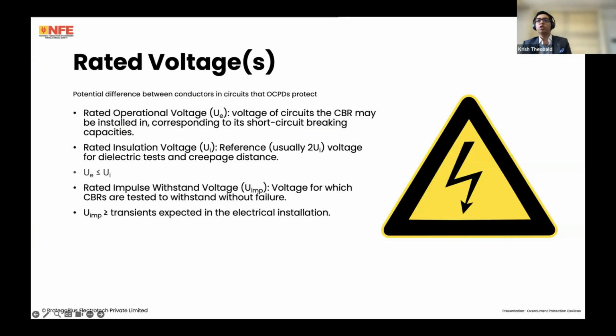There's also a rated insulation voltage, which is what is used by manufacturers for testing, for the dielectric test and the creepage test. Usually it's a reference voltage, so they test at 2 times the rated insulation voltage. Also remember that the rated insulation voltage will always be greater than the rated operational voltage. And remember, these are usually given as line to line, so phase to phase voltages.